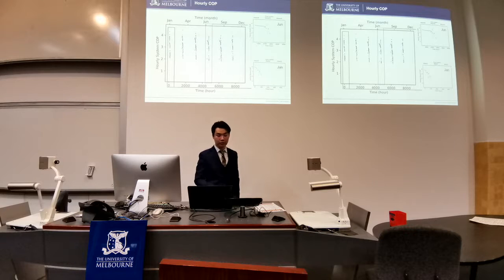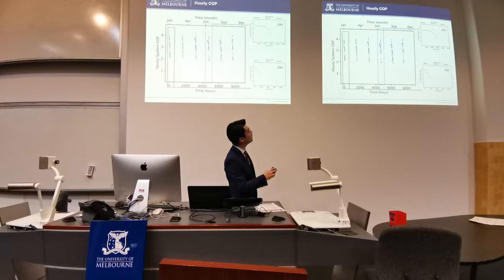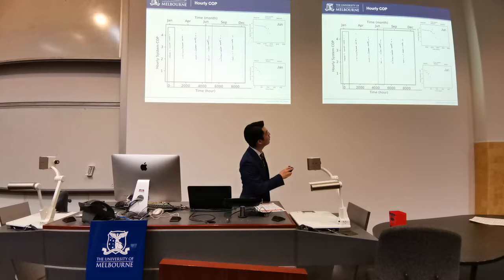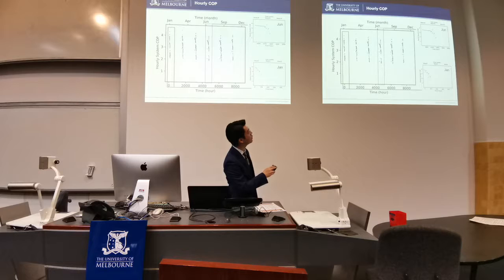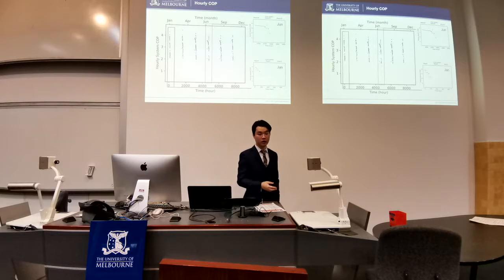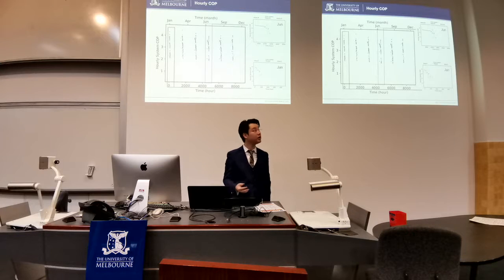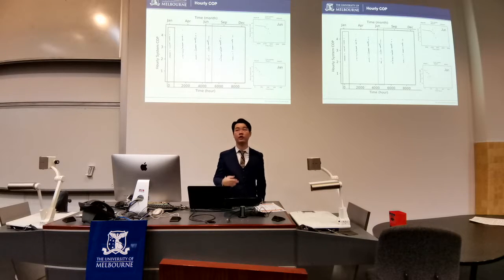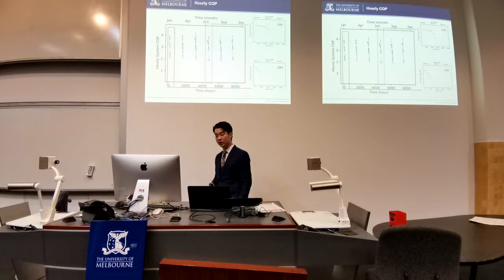We can also look at the hourly COP of the system. Say at the beginning of the year, we have some hourly COP over here, and then in the middle of the year, if we're starting a batch, we will see the hourly COP over here. We can see that over here, the COP is slightly larger than this one, and it's much more uniform. That is because in June, when you're starting a batch over here, your ground source heat pumps are under continuous operation because the heating load is high. And if you're starting in January, because your heating load is not that high, some of the heat pumps may be switching on and off. They're not under continuous operation, and that has an impact on the COP.